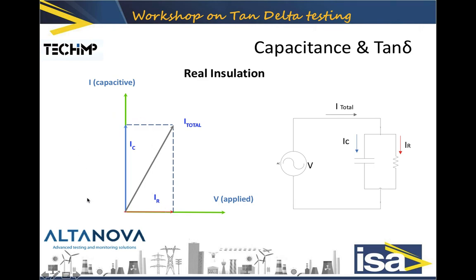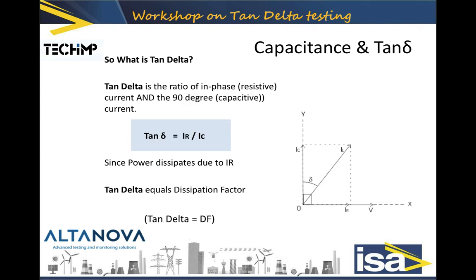We now define tan delta. The angle delta that we look at is a very small angle — usually less than 1 degree. The tangent of this angle, tan delta, equals IR over IC. Another name for tan delta is dissipation factor; they are synonyms. So tan delta equals the ratio of the in-phase resistive current to the 90-degree capacitive current.